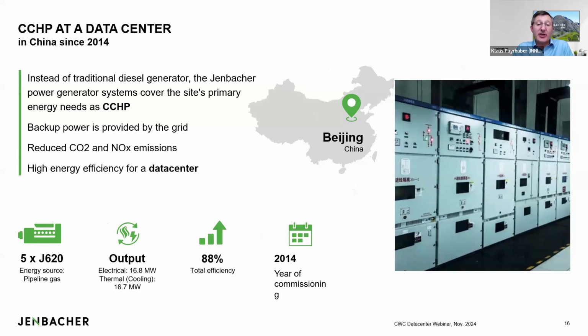Going to other regions, like in China, in Beijing, this is an installation with CHP technology. Our local partners in China installed 5 620 engines producing close to 17 megawatts of electricity, using the waste heat from the engine to drive an absorption chiller to produce about 17 megawatts of cooled water, for a local data center in Beijing. The total efficiency, or fuel utilization rate, is very high, close to 90%. And of course, there is a lot of CO2 emission savings.